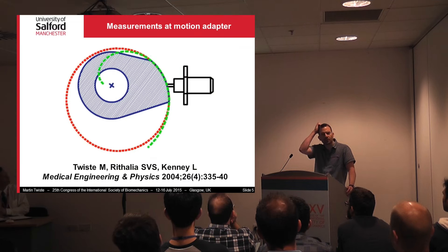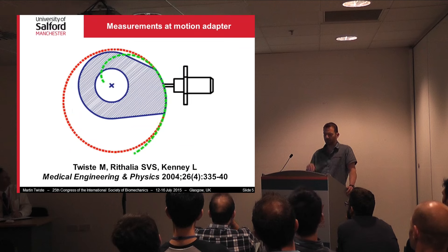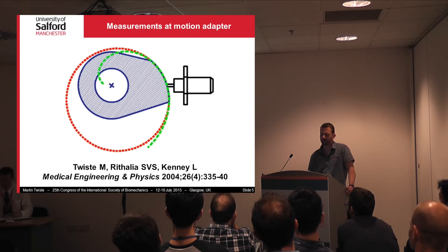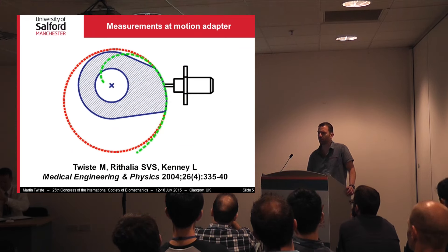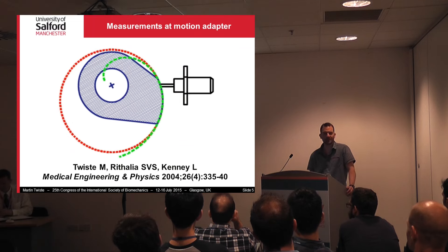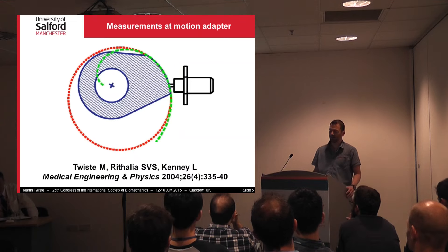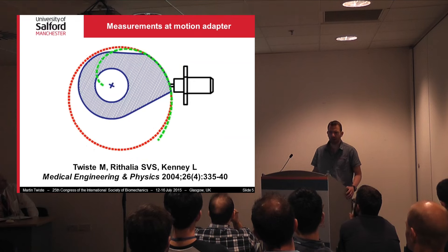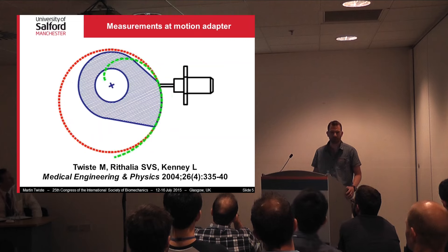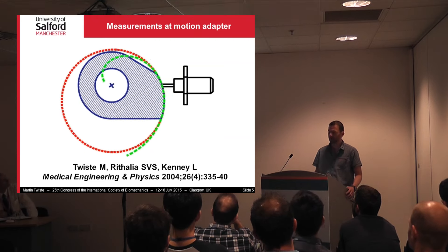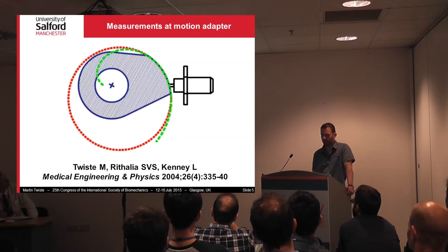Here's a diagram showing the action of the motion adapter and the plate cam as seen from above. The blue cross in the middle is the center of the motion adapter. You can see the transducer mounted perpendicular to the longitudinal axis, with its plunger being depressed due to motion of the cam. The cam was manufactured using a lathe giving a fixed radius, represented by the red line. Ideally, for a linear output from the displacement transducer you should have a spiral radius as indicated by the green line. There's a slight offset between the green and red lines, but calculations showed it was very little and didn't affect measurement accuracy, as demonstrated in the referenced paper.